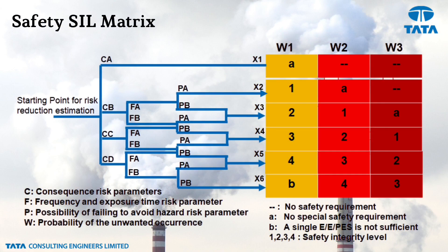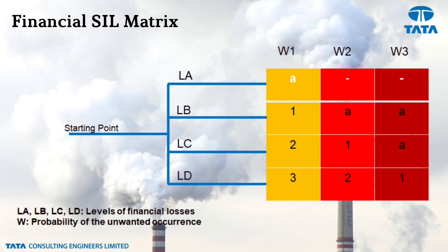For determining safety SIL, a matrix is used with four parameters: C (consequence risk parameter), F (frequency and exposure time risk parameter), P (probability of failing to avoid the hazard), and W (probability of the unwanted occurrence). Based on the inputs for each loop, the SIL level is determined using this matrix.